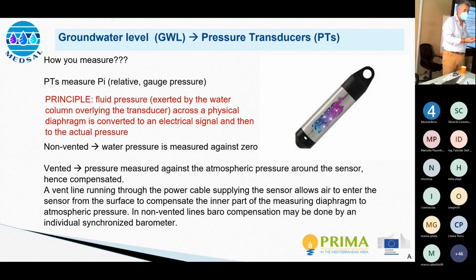So you need to make sure that what is being measured has been cleared of the changes of barometric pressure, that is atmospheric pressure. And this is important basically when you are monitoring in confined aquifers. If you are monitoring in unconfined aquifers, this becomes negligible. But in confining units, this is very important. So in the case of the simple measurement of groundwater level without the compensation of barometric pressure, what you get is the mixed effect of barometric pressure and the pressure exerted by the column of water.